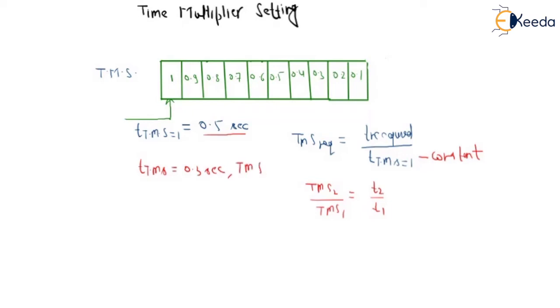So TMS required, TMS2 required upon TMS1 is equal to 1, when T2 required will be 0.3 and T1 is equal to 0.5. So this is nothing but 0.6. So TMS2 will be equal to 0.6.